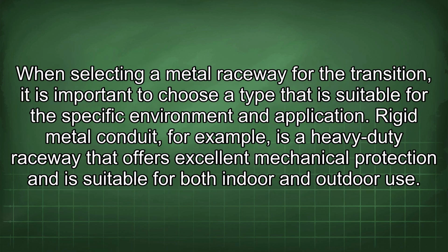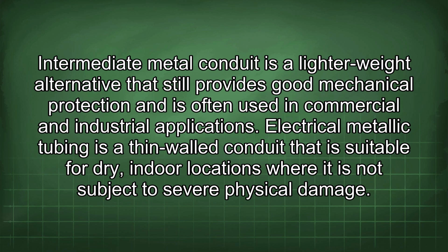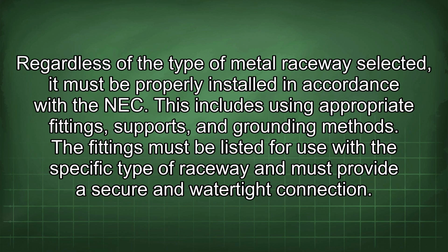When selecting a metal raceway for the transition, it is important to choose a type that is suitable for the specific environment and application. Rigid metal conduit, for example, is a heavy-duty raceway that offers excellent mechanical protection and is suitable for both indoor and outdoor use. Intermediate metal conduit is a lighter-weight alternative that still provides good mechanical protection and is often used in commercial and industrial applications. Electrical metallic tubing is a thin-walled conduit that is suitable for dry, indoor locations where it is not subject to severe physical damage. Regardless of the type of metal raceway selected, it must be properly installed in accordance with the NEC. This includes using appropriate fittings, supports, and grounding methods.